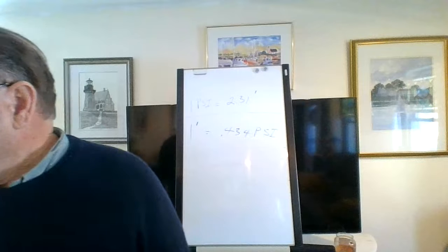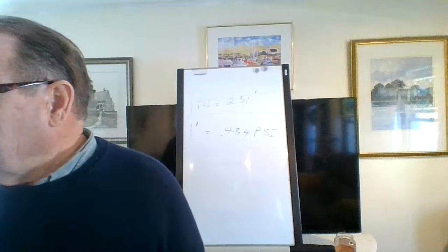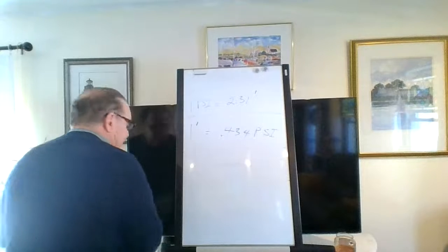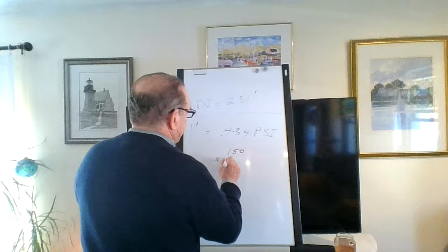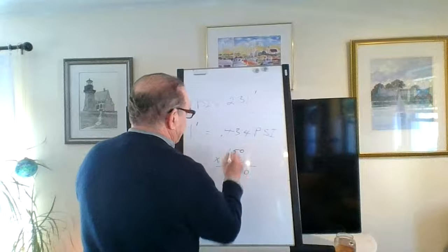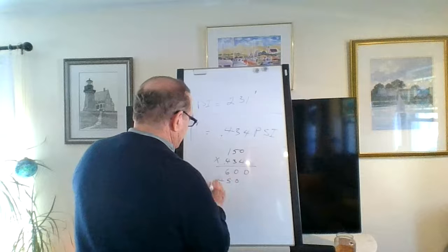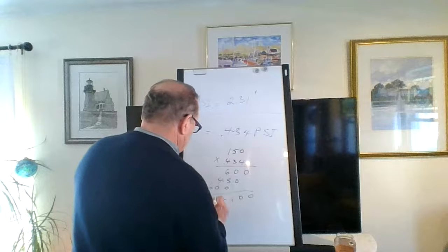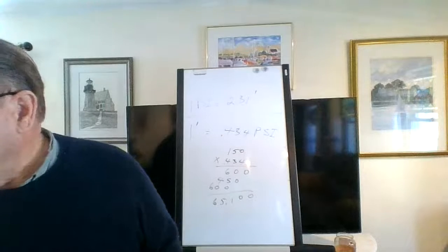Okay, so that's 150 feet times 0.434. Okay, comes up to 65.1 psi.